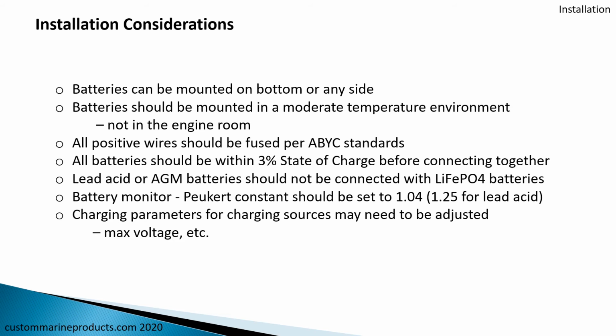So here's some installation considerations. The nice thing about these batteries is that there's no fluid in them, and so they can be mounted on their bottom, their side, any side, so you can mount them in any way you wish. We suggest that they not be mounted in an engine room where they're going to get very warm. It's much better in a moderate temperature environment than in a hot engine room for the overall life of the battery. We suggest that you, same as with a lead acid or AGM battery, fuse the positive wires per the ABYC standards. And we suggest, as I mentioned earlier, that they be within a 3 to 5% state of charge of each other before connecting them together in series or parallel.